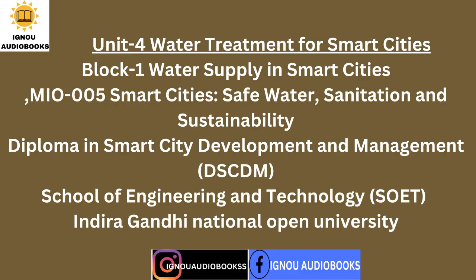Micro screens. These screens are rotating drum screens having a speed of 4 revolutions per minute. These screens are continuously backwashed, operating in gravity flow conditions. The openings of the filtering fabrics are 10 to 35 micrometers and they are fitted on the periphery of the drum. The influent enters through the drum lined with fabrics. The retained solids are collected through backwashing and transported for disposal.